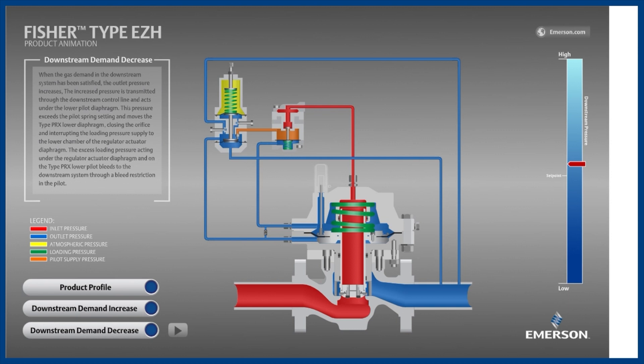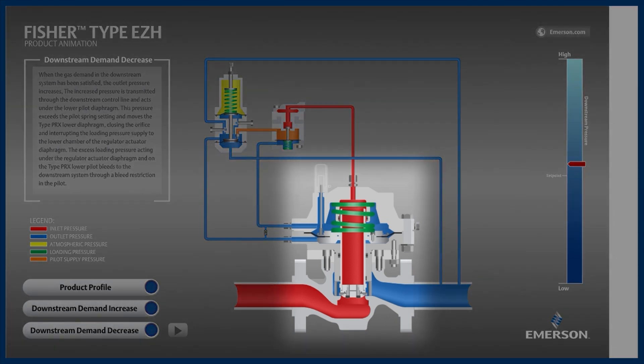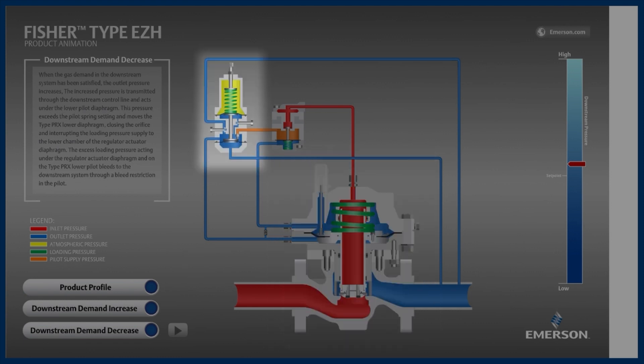In this video, we will learn how the Fisher type EZH pressure regulator works through this product animation. The EZH is a pilot-operated regulator, consisting of a main valve installed in the flowline, plus a pilot above. Also depicted is a pre-pilot, known as a pilot supply regulator, which provides the pilot with a steady, reduced supply pressure, shown in orange.